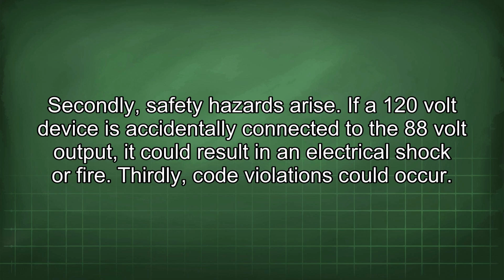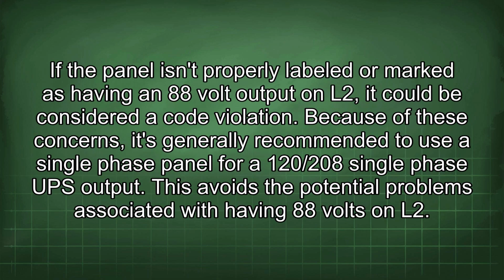Secondly, safety hazards arise. If a 120-volt device is accidentally connected to the 88-volt output, it could result in an electrical shock or fire. Thirdly, code violations could occur. If the panel isn't properly labeled or marked as having an 88-volt output on L2, it could be considered a code violation. Because of these concerns, it's generally recommended to use a single-phase panel for a 120/208 single-phase UPS output. This avoids the potential problems associated with having 88 volts on L2.